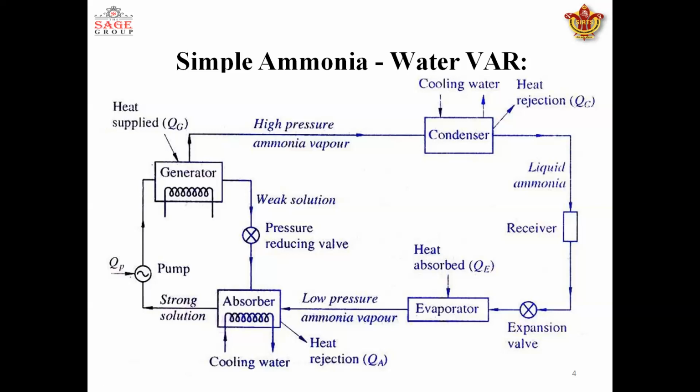The temperature will also drop, and thus the low pressure and low temperature ammonia liquid will be vaporized inside the evaporator, and thus producing the refrigerating effect.